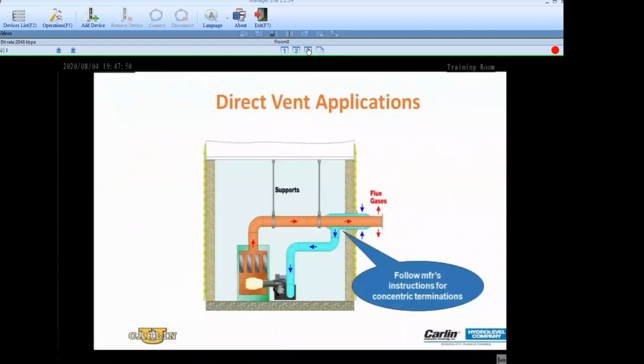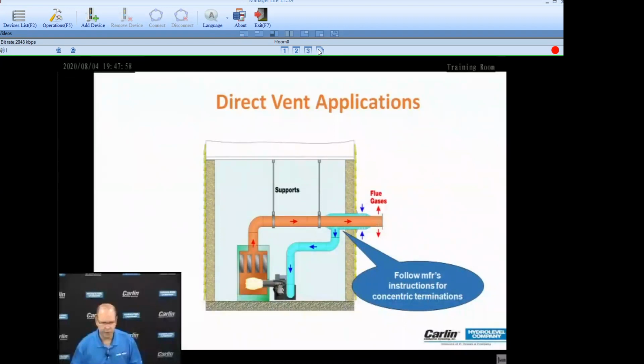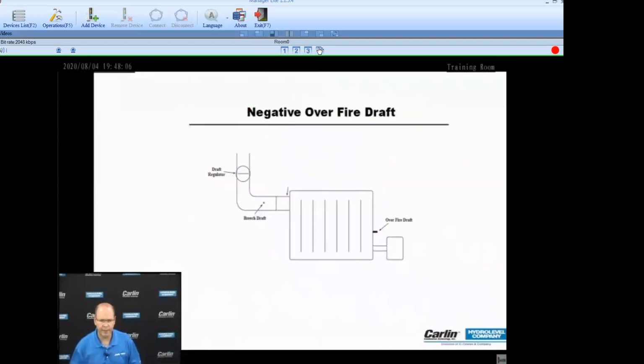So it's, again, relative that when you walk into an application, you understand the equipment that you're working on, and you have a really good understanding of what the specs are for that appliance. You've got to make some kind of an adjustment for spec. In a negative draft appliance, the flue gases travel through the boiler quite easily. And that's what they're designed to do. So your excess air is set up minimally for a negative draft appliance.